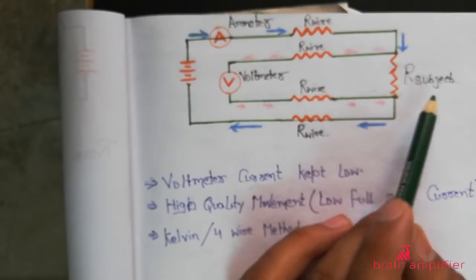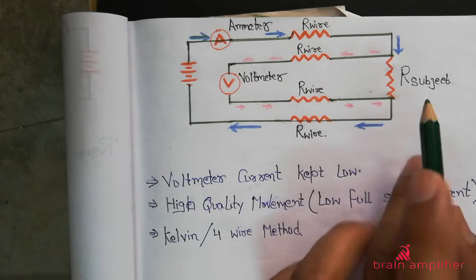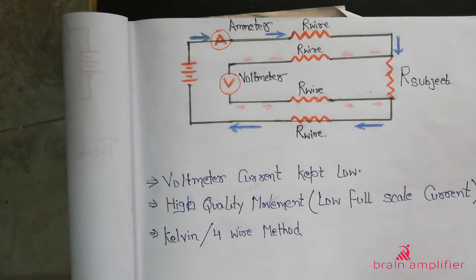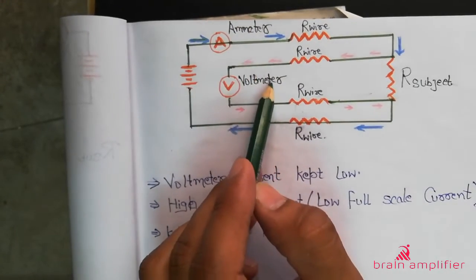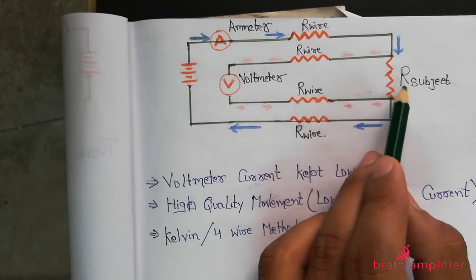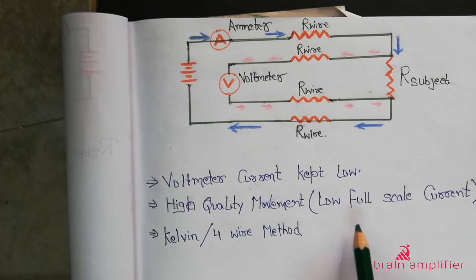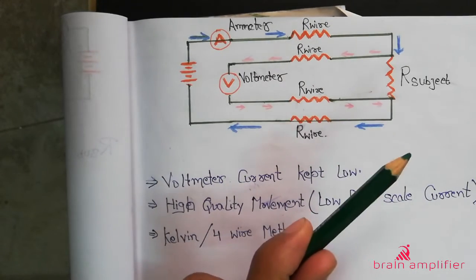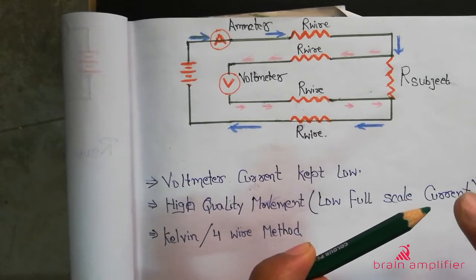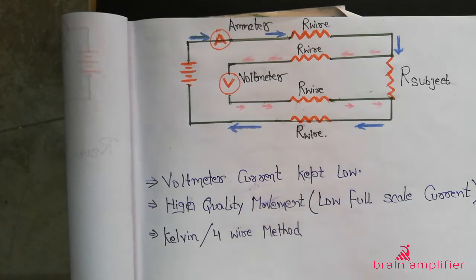If I have to measure a very low resistance — in the milli-ohm or micro-ohm range — the current I need to supply is very high. Because resistance is very low, the current to be passed is very high. So the current leads are thicker and the voltage leads are thinner. This is how we can accurately measure very low resistance values. This method is also called the Kelvin measurement method.